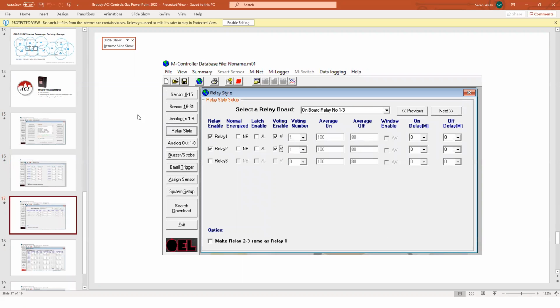Then you have to set up your relays. You can determine how many relays you need - the M controller has 3 relays on board. I always say use the voting mode. What that means is, let's say you have 8 sensors - when you put it in voting mode and set the voting number, it means that if any one of those sensors detects the gas, it's going to turn on the relay.